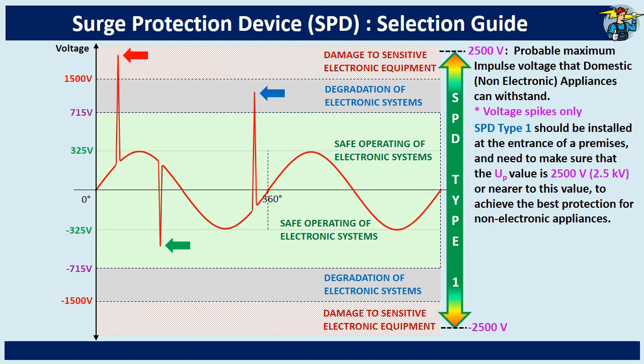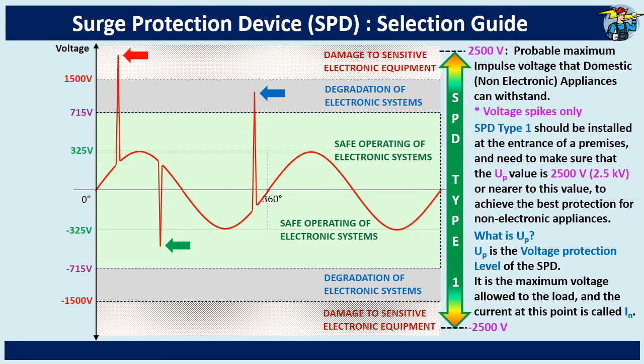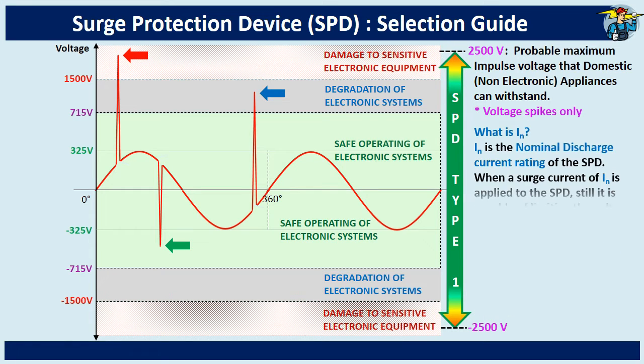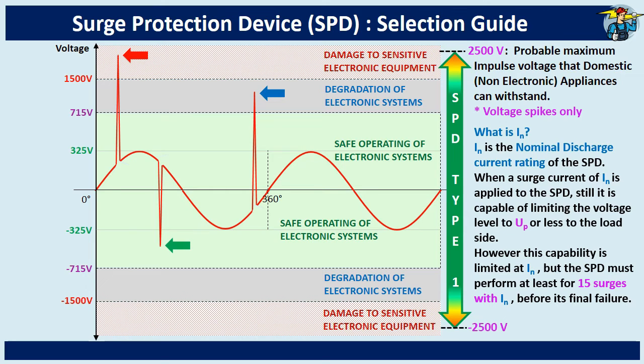So, what is UP? UP is the voltage protection level of the SPD. It is the maximum voltage allowed to the load, and the current at this point is called IN. IN is the nominal discharge current rating of the SPD. When a surge current of IN is applied to the SPD, it is still capable of limiting the voltage level to UP or less on the load side. However, this capability is limited at IN. The SPD must perform for at least 15 surges with IN before its ultimate end of life.